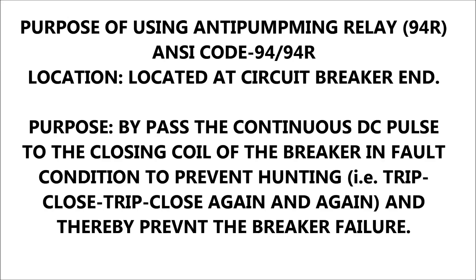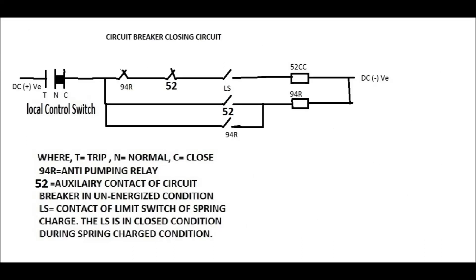The anti-pumping relay, normally represented in ANSI code as 94 or 94R, is located at the breaker end. Its main purpose is to bypass the continuous DC pulse to the closing coil of the breaker in fault conditions, to prevent hunting — that is, trip-close-trip-close again and again — and thereby prevent failure of the breaker.